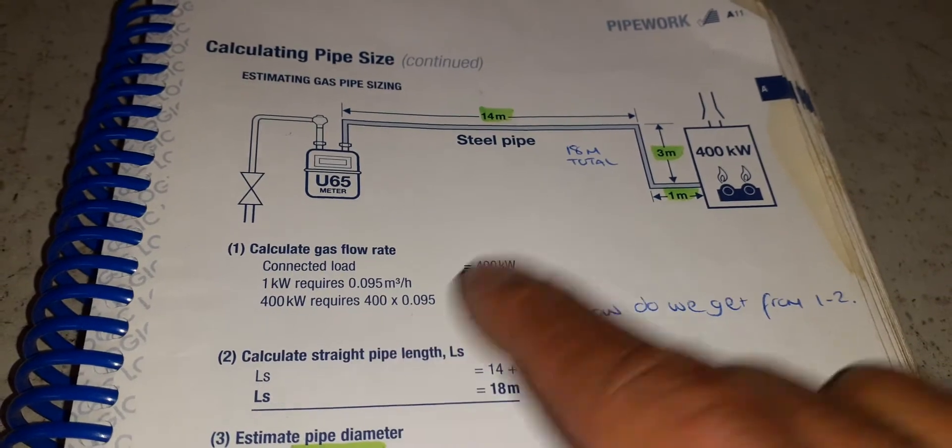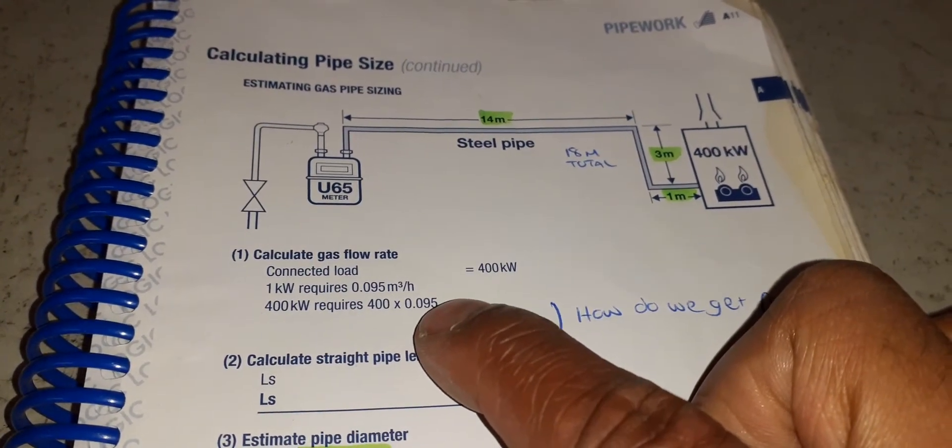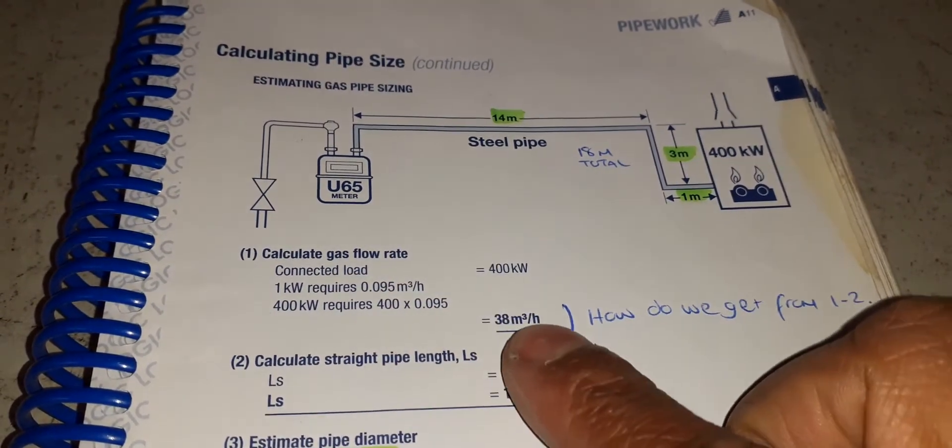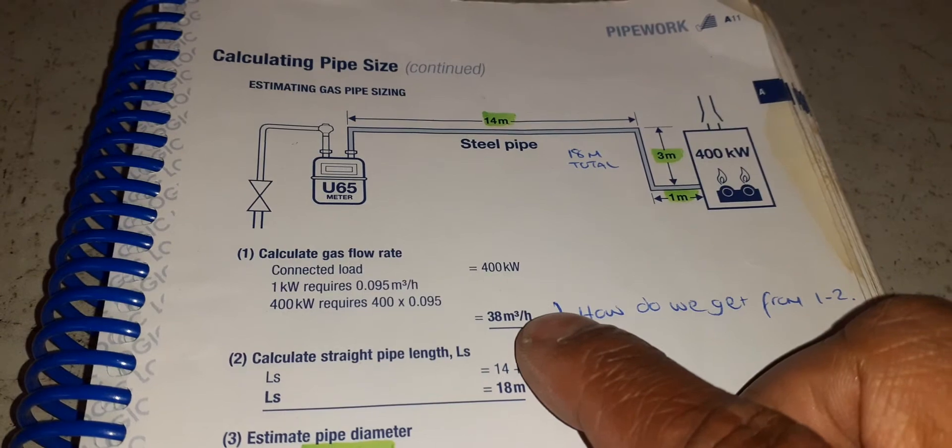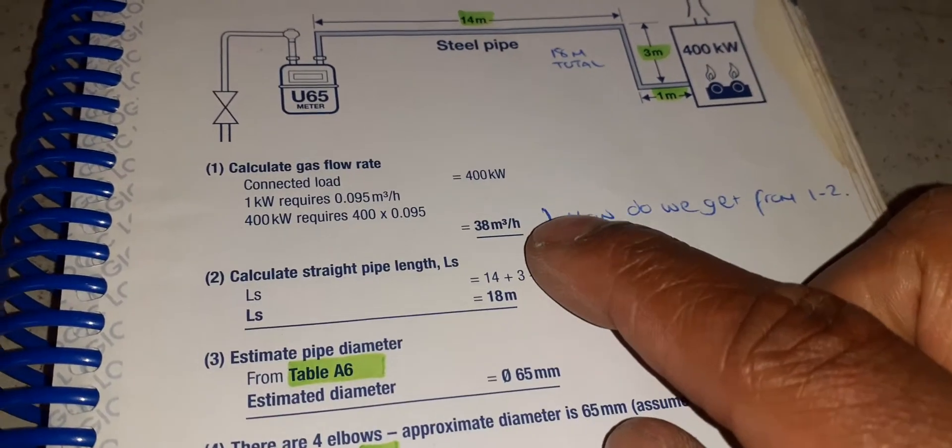So we just got 400 kilowatts that we have here and we times it by the 0.095 that is required per kilowatt, and we end up with 38 meters cubed of gas an hour.